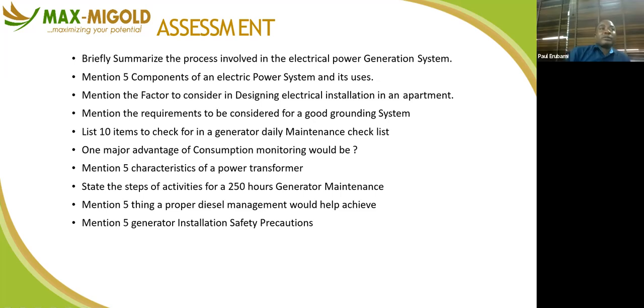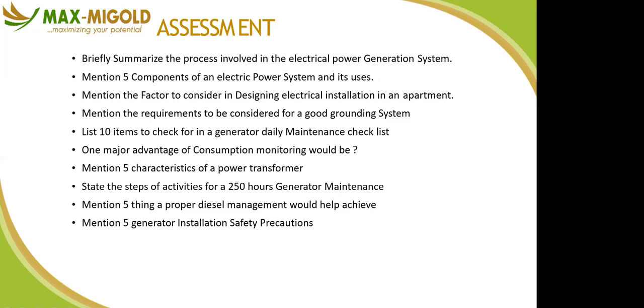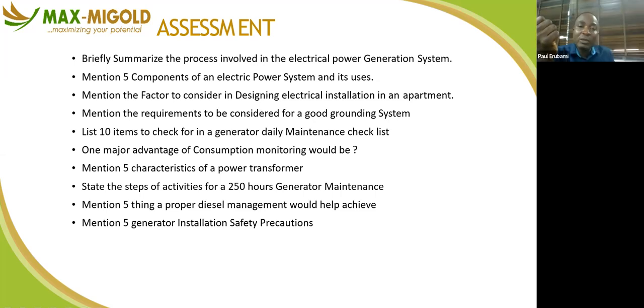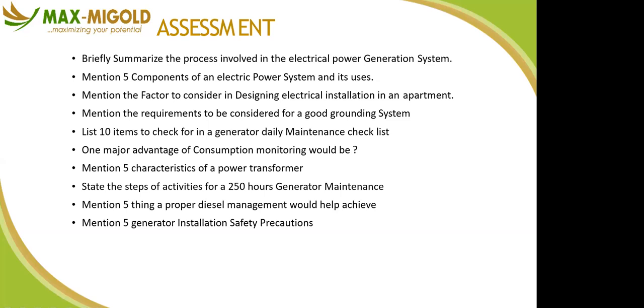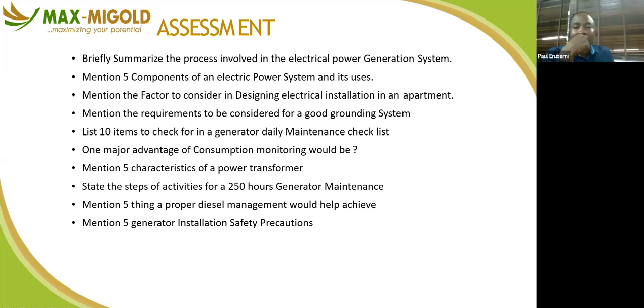You are killing those generators. It's not up to even 30%, and a generator is recommended to be loaded up to 45%. So you don't need those two generators on that site. Is the facility fully occupied, or are you still expecting tenants? Fully, it's fully occupied. So those two generators are not meant for that site.